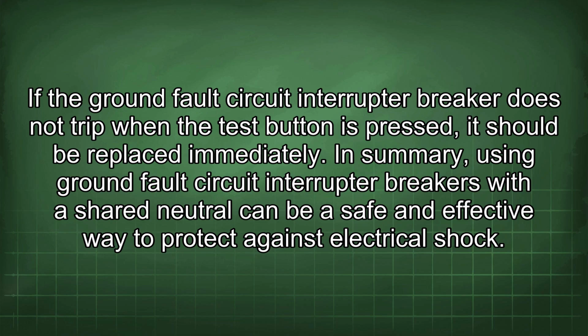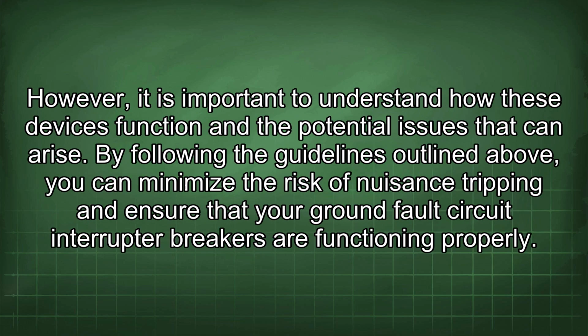In summary, using ground fault circuit interrupter breakers with a shared neutral can be a safe and effective way to protect against electrical shock. However, it is important to understand how these devices function and the potential issues that can arise. By following the guidelines outlined above, you can minimize the risk of nuisance tripping and ensure that your ground fault circuit interrupter breakers are functioning properly.